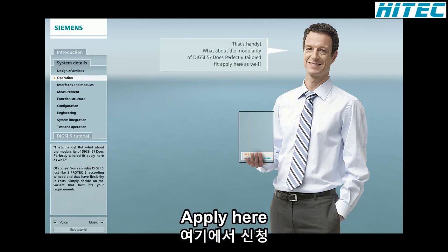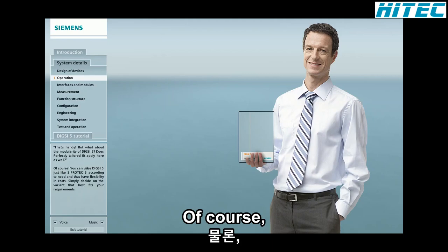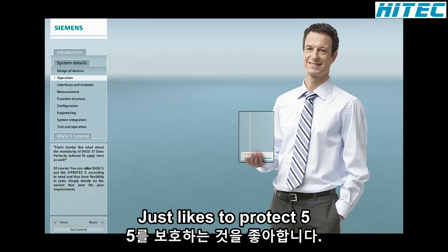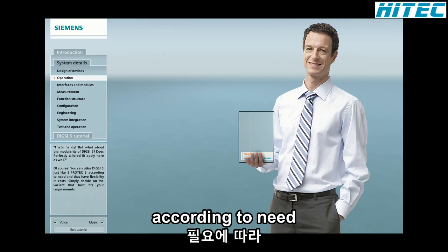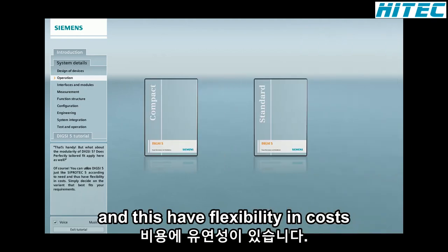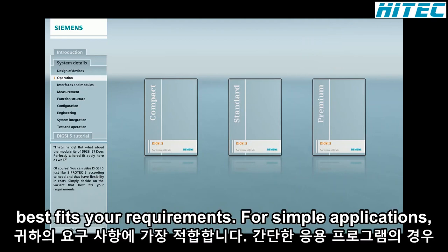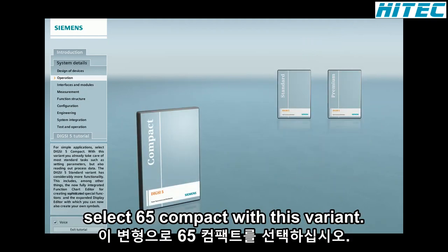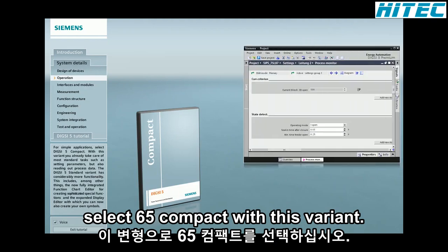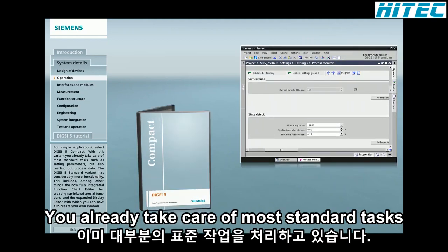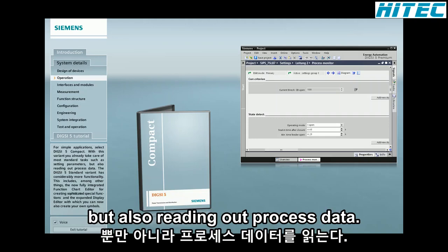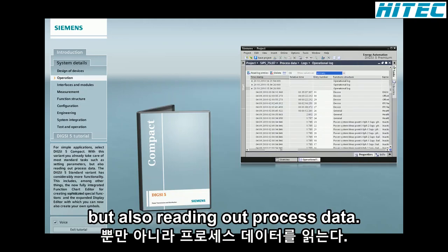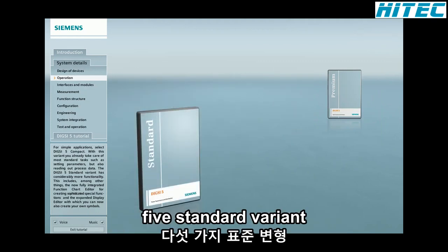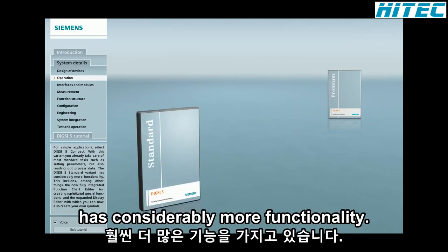Does perfectly tailored fit apply here as well? Of course, you can utilize DIGSI 5 just like SIPROTEC 5 according to need and thus have flexibility in costs. Simply decide on the variant that best fits your requirements. For simple applications, select DIGSI 5 Compact. With this variant, you already take care of most standard tasks, such as setting parameters, but also reading out process data. The DIGSI 5 Standard variant has considerably more functionality.